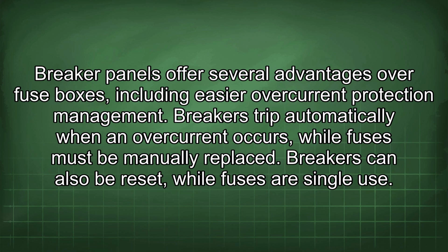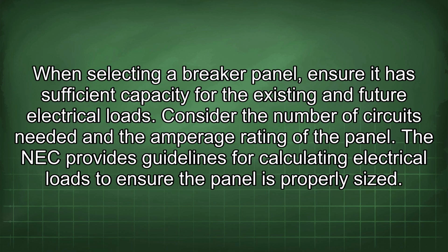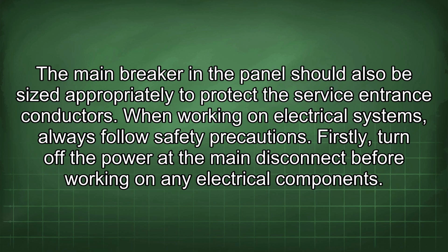Breaker panels offer several advantages over fuse boxes, including easier overcurrent protection management. Breakers trip automatically when an overcurrent occurs, while fuses must be manually replaced. Breakers can also be reset, while fuses are single-use. When selecting a breaker panel, ensure it has sufficient capacity for the existing and future electrical loads. Consider the number of circuits needed and the amperage rating of the panel. The NEC provides guidelines for calculating electrical loads to ensure the panel is properly sized. The main breaker in the panel should also be sized appropriately to protect the service entrance conductors.